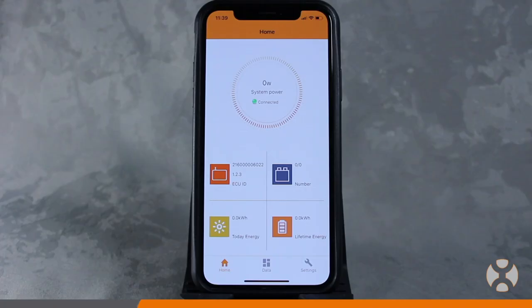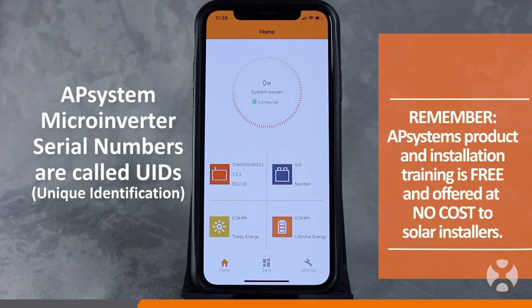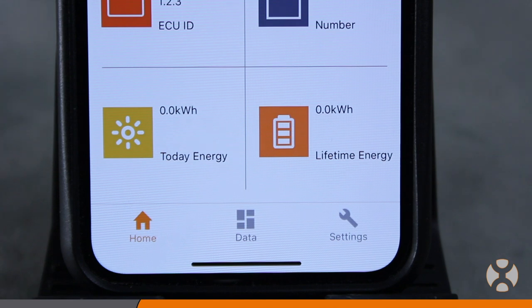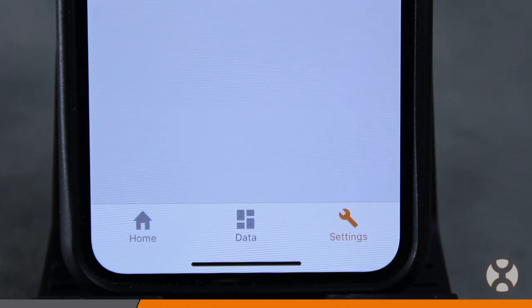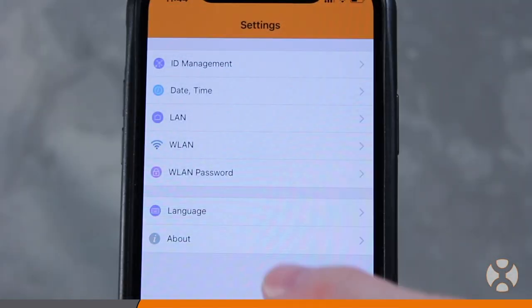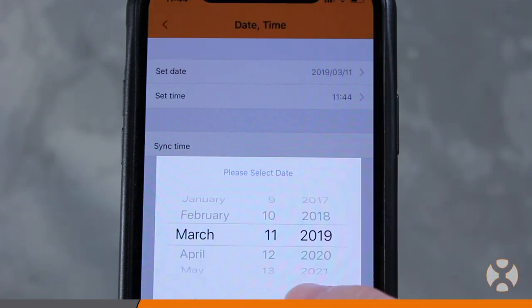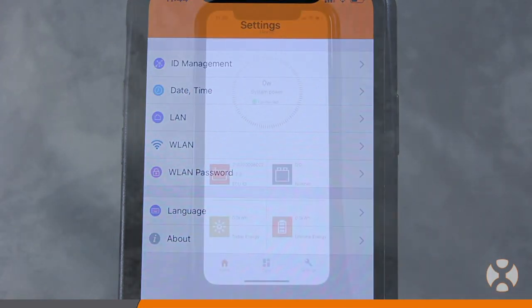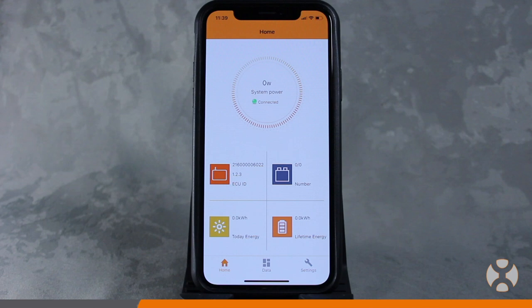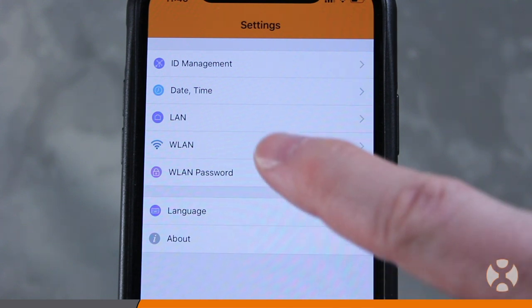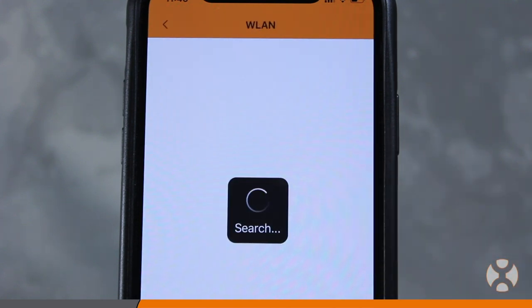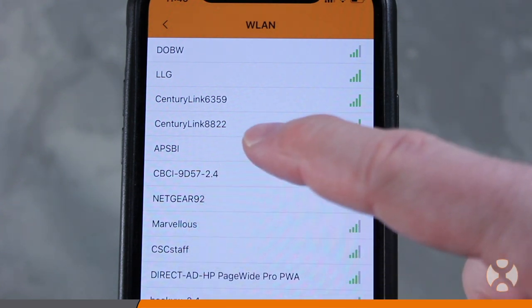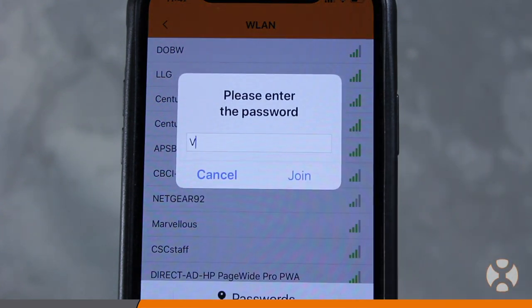If this is your first time configuring this ECU, you must first set the date and time before scanning inverter UID serial number codes. To do this, go to Settings located on the bottom right of the home screen, touch the option for date and time, and set both the date and time so that they're current with your time zone. If a wired Ethernet connection is not available and the installer chooses to use the Wi-Fi function to connect the ECU to the internet, touch the WLAN option under Settings and look for the homeowner or site's wireless signal broadcast. Enter the password and touch Join.